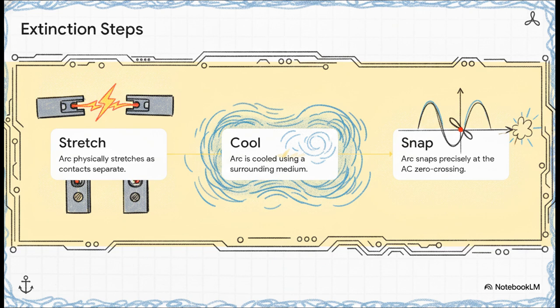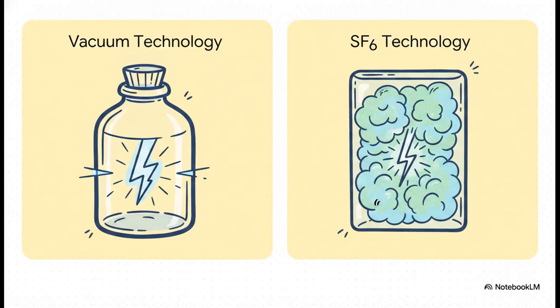The breaker waits for the exact microsecond the AC waveform crosses zero, and then it snaps the arc out of existence. Every single breaker technology out there exists to make that zero crossing kill permanent, instead of letting the arc restrike. To make sure that zero crossing kill sticks, marine switchgear basically relies on two primary ambient substances.